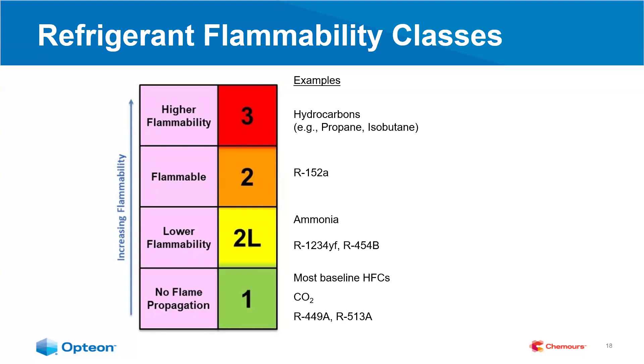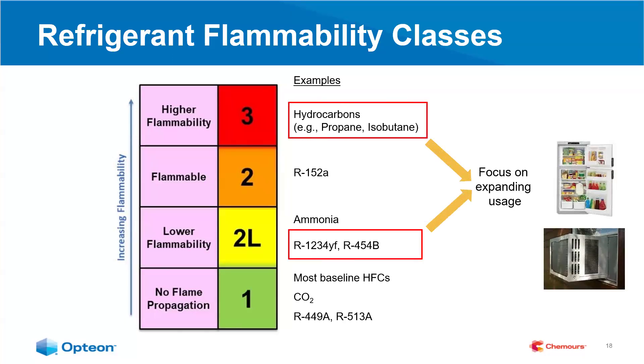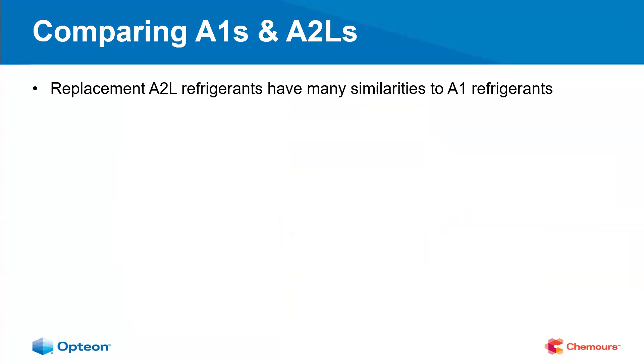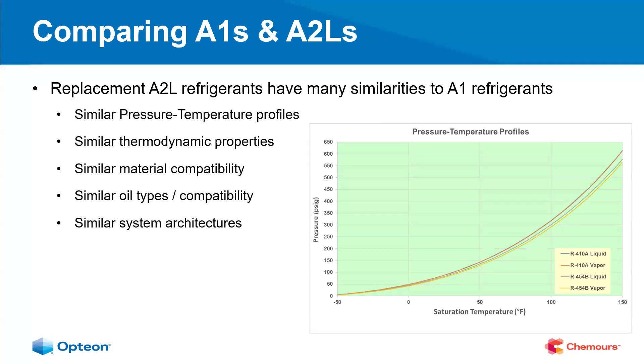The industry has spent over the last decade trying to safely enable the broader use of A2L and A3 refrigerants, transitioning from smaller charge applications historically used in domestic refrigerators or window units into larger systems. A2Ls were really designed to do two things: mirror the performance of HFCs as closely as possible while also minimizing the risk associated with flammability. When you compare A1s and A2Ls, they have a tremendous amount of similarities — similar temperature-pressure profiles, similar thermodynamic properties, similar material compatibility, and they often use the same oil types and system architectures.